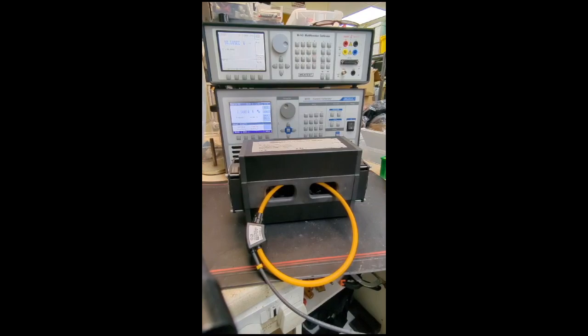It's the device on the top, the device on the bottom. The larger one is a 100 amp source that's regularly sent away to an accredited calibration lab to have certification to ensure that it's operating to spec. And I will say that all this equipment that we're using is many, many more times accurate than it need be for the application that we are actually testing.